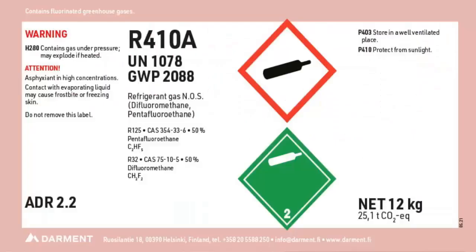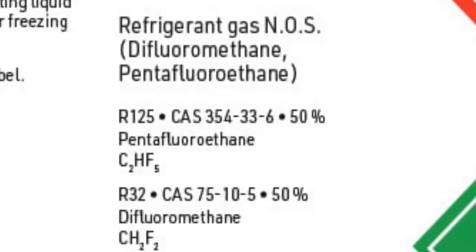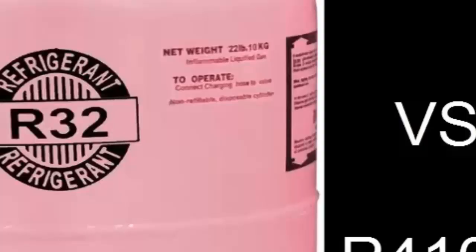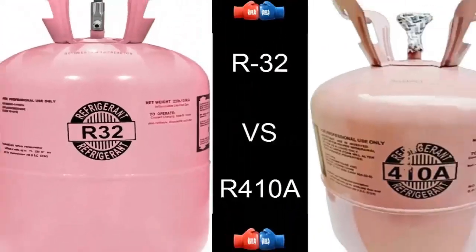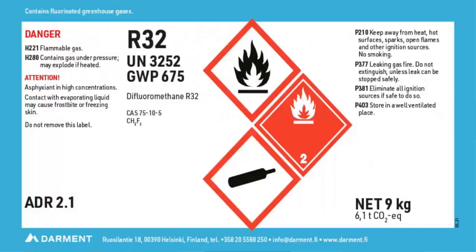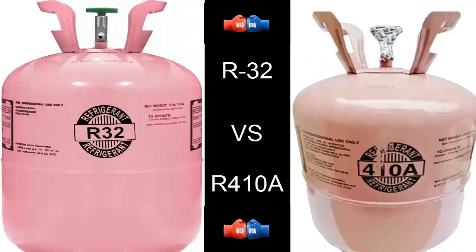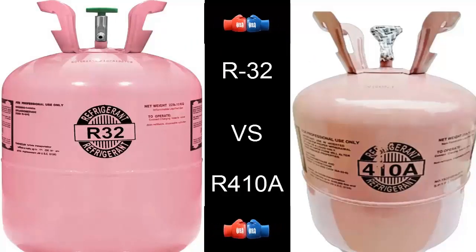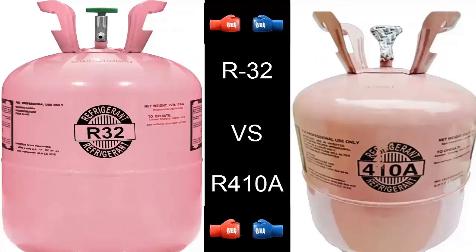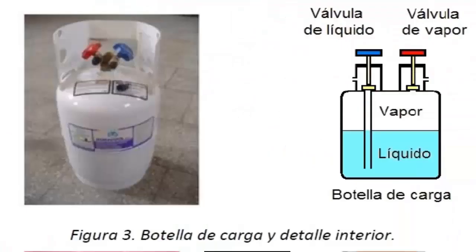Let's start by stating that R410A is a blend of two gases, in contrast to R32 refrigerant, which is an unadulterated gas composed of a single element. R410A is predominantly comprised of R32 and R125 in an equitable proportion of 50% for each component. R32, being a pure gas, can be charged in either liquid or gaseous state.